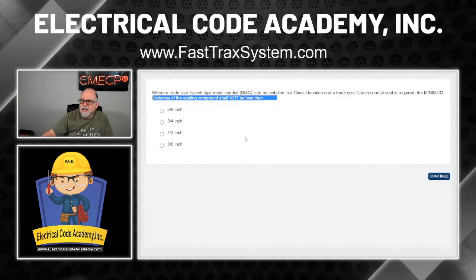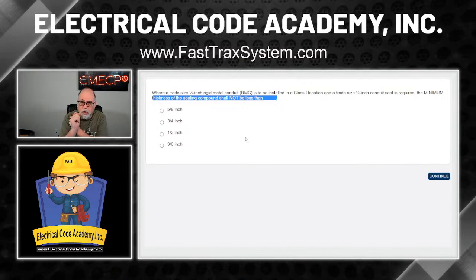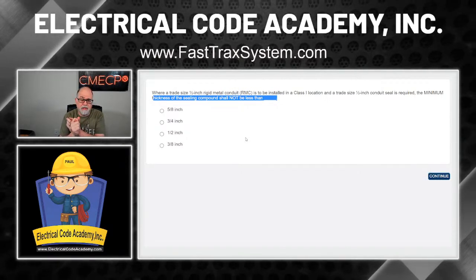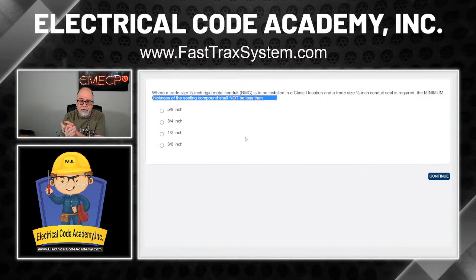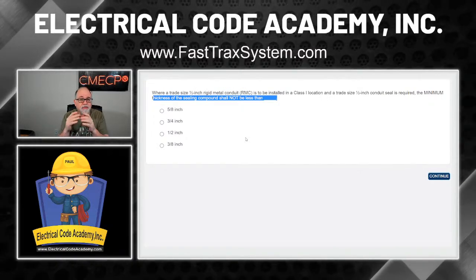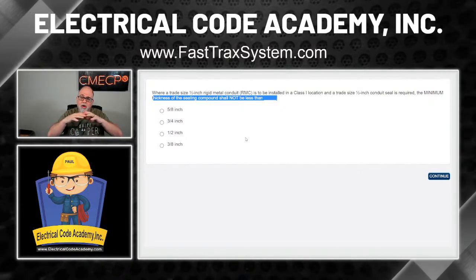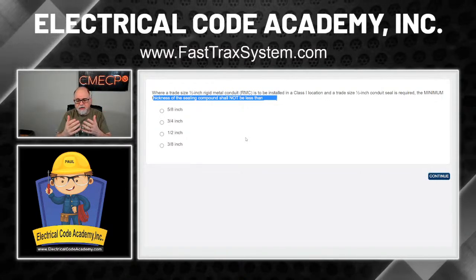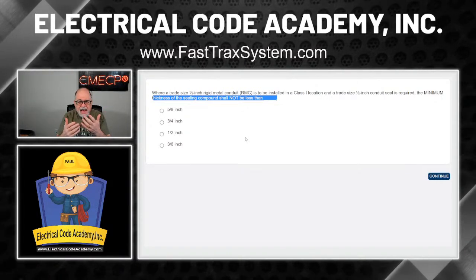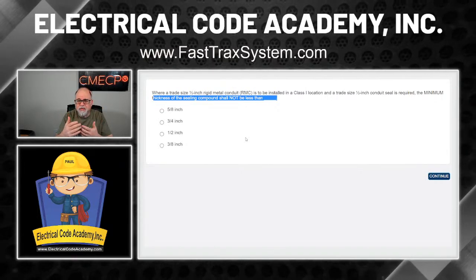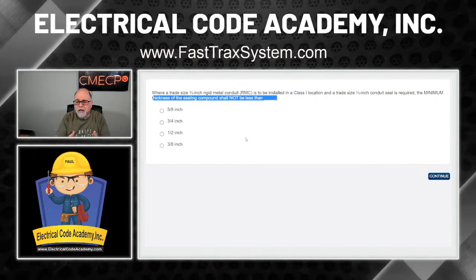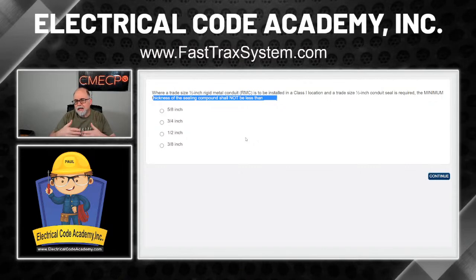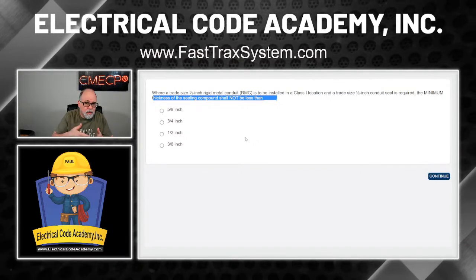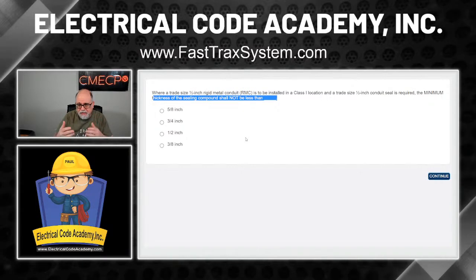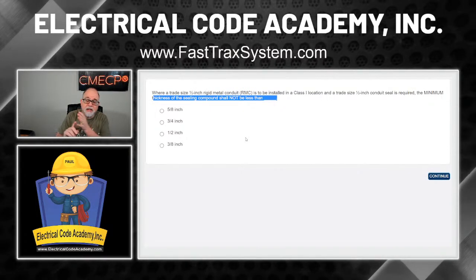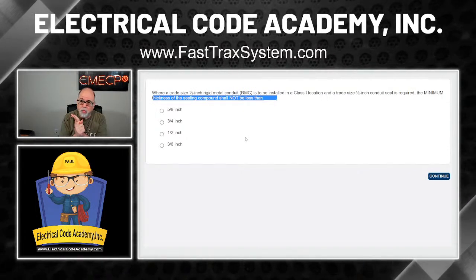So the first thing that triggers for me is it's Class 1. All right, so you need to know the article that deals with Class 1. That's Article 501. Okay, hazardous locations starts at 500. That's what gives you all of the things that constitute the different types of gases and all this, and their classification. Gives you some general rules. And then you start getting into Class 1, Class 2, Class 3, which is 501, 502, 503, that type of thing. So in our case, we know it's Class 1, so that's 501.